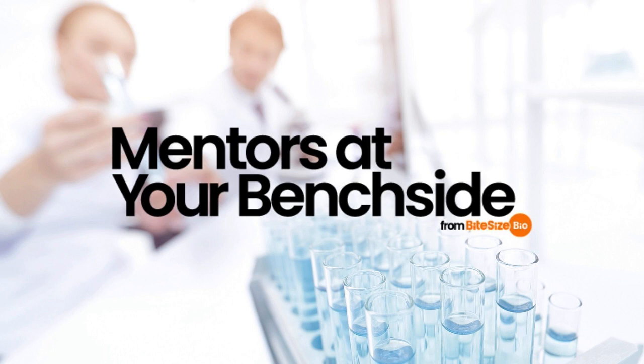Now, sometimes you need to deep clean your lab balance, and how often deeper cleaning of your scales is required will depend on a couple of factors. How often they're used and how good you and other members of the lab are at keeping up daily maintenance are key. Even if they look okay, be sure to give them a more thorough clean every couple of months or so. And we've got a list of do's and don'ts for cleaning your lab balance. First, the do's. Moisten a thin wipe like a Kim wipe with purified water and carefully clean the pan and around the scales, and then wipe it dry. Do remove the pan to facilitate a more thorough cleaning to maintain your lab balance.